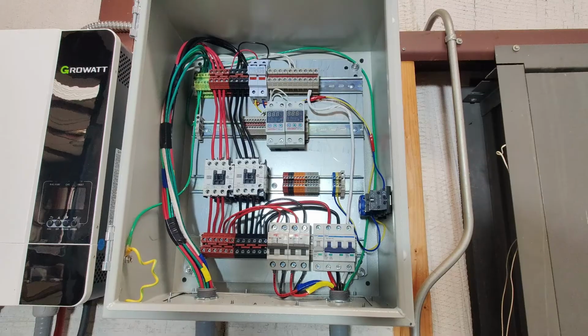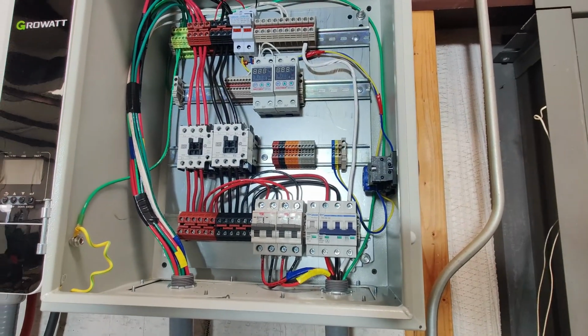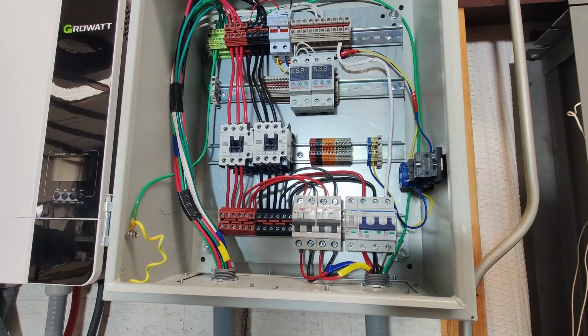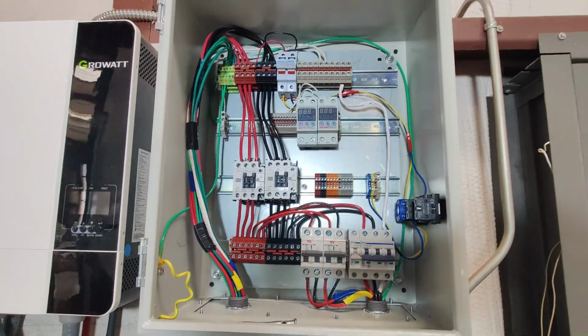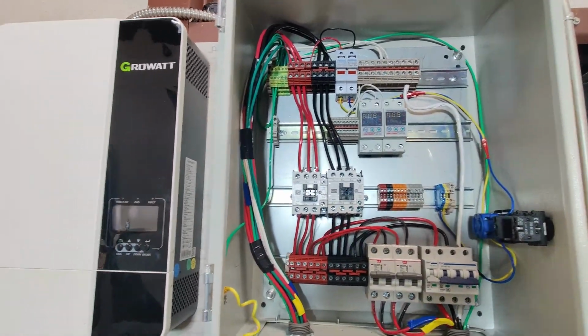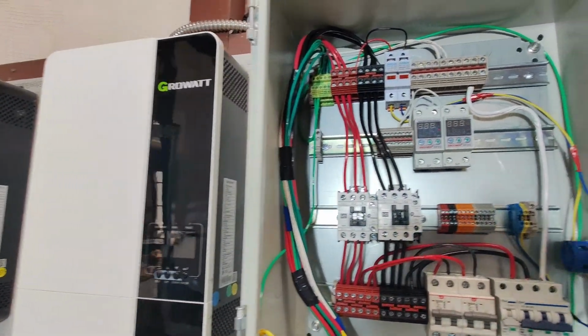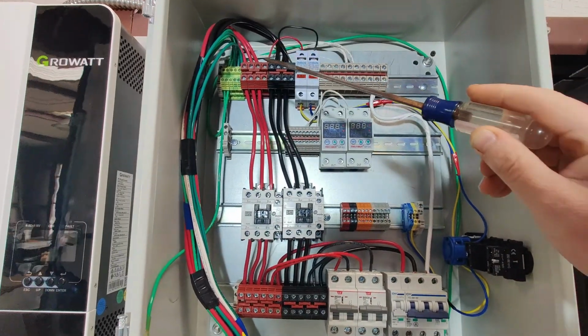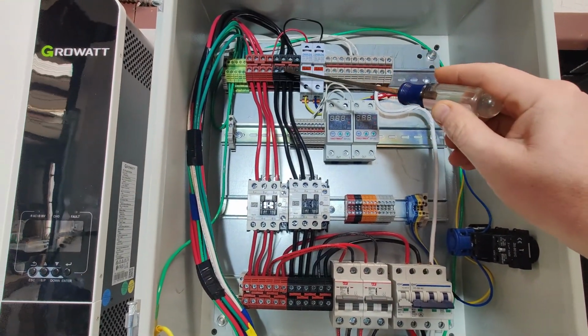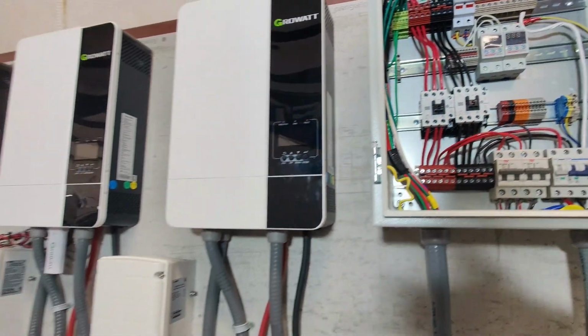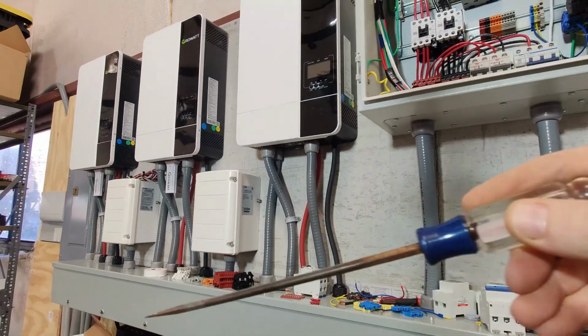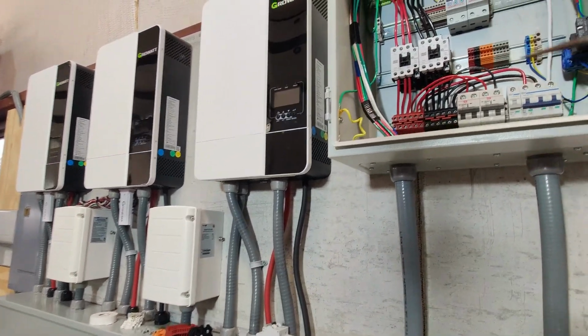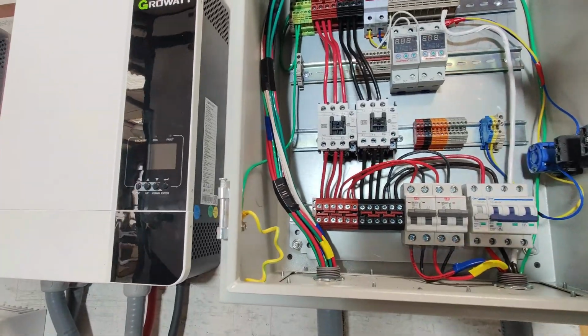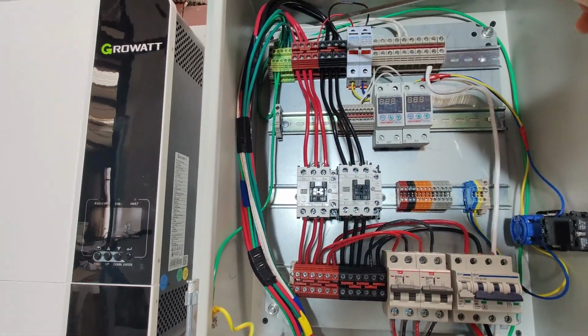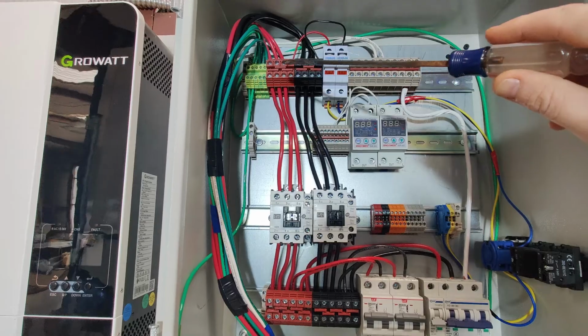So what we're going to be doing is showing you how to wire up the control side of this circuitry. And you see I've got a couple of things already wired up in here. Maybe I've got to grab my pointer here. So we already have our hot legs that come out of the inverters, and those come down through the wire cableway, come up into here, and they come into this terminal block where they are paralleled together.